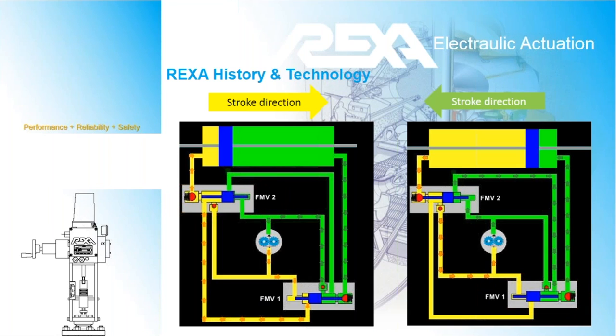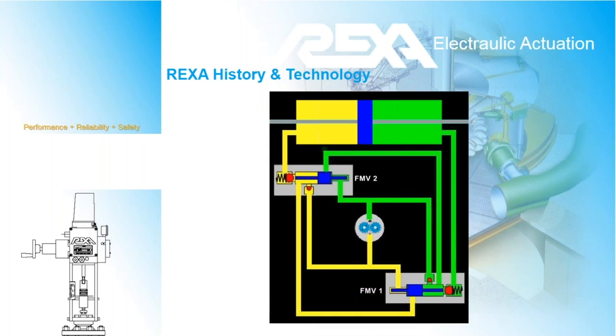Now look at the circled areas. Notice how the spools are engaged this time. The spool pushes up against the seated ball check while simultaneously redirecting the oil so it can be transferred to the other side of the cylinder, where the spool restricting the flow is now open. In this snapshot, the actuator has reached target position. It is hydraulically locked in place. Both spools are seated and the ball checks are isolated on each side of the cylinder.